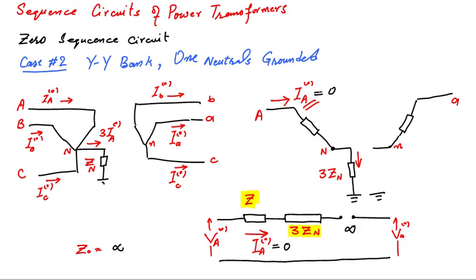Okay. Now why has the current become zero when one of the neutral points becomes open? It is very simple to explain. Current cannot exist at only one end of the transformer. If it is flowing through one of the windings, then its counterpart must exist on the other side of the transformer winding. Zero sequence current cannot exist here in this case. So this is our conclusion.